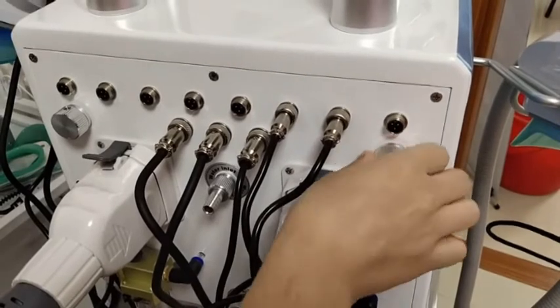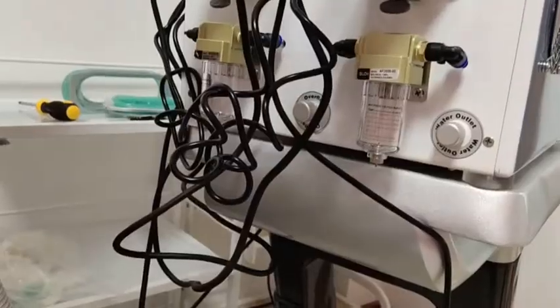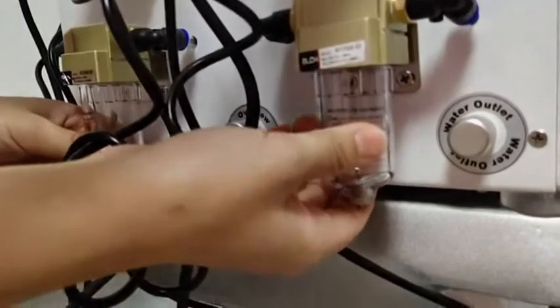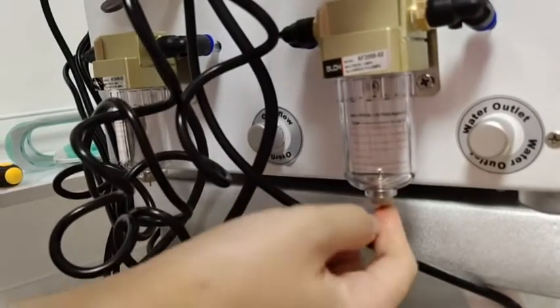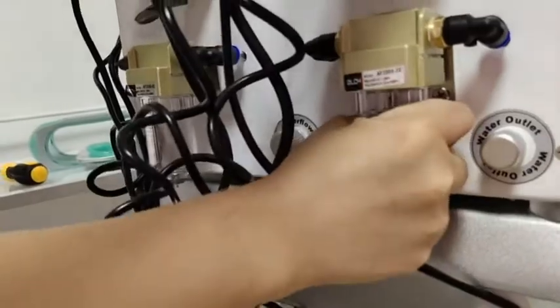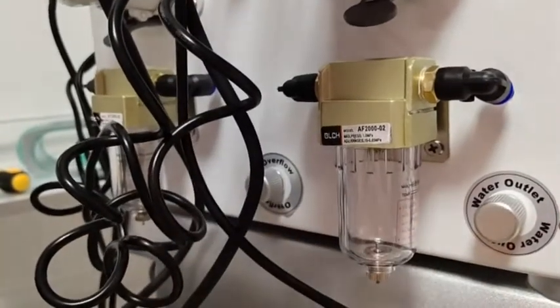These two filters are important — there must not be any water in the bottle. If there is water, there are two ways to remove it: first, use your finger to touch the needles and the water will come out; second, unscrew the bottle and pour out the water, then reconnect.